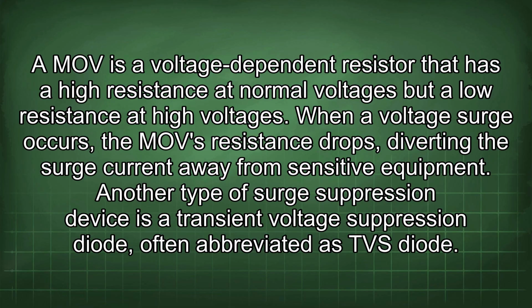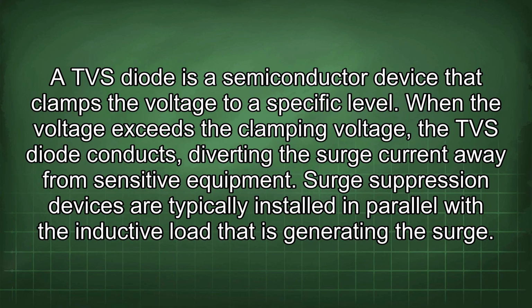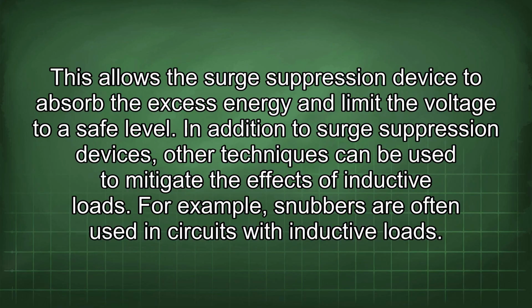Another type of surge suppression device is a transient voltage suppression diode, often abbreviated as TVS diode. A TVS diode is a semiconductor device that clamps the voltage to a specific level. When the voltage exceeds the clamping voltage, the TVS diode conducts, diverting the surge current away from sensitive equipment. Surge suppression devices are typically installed in parallel with the inductive load that is generating the surge. This allows the surge suppression device to absorb the excess energy and limit the voltage to a safe level.